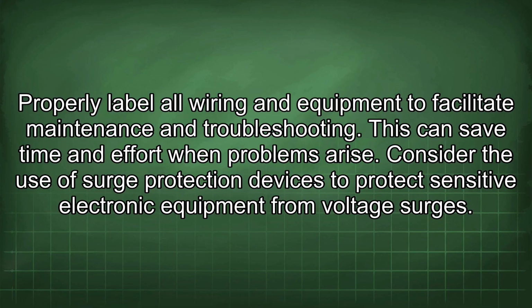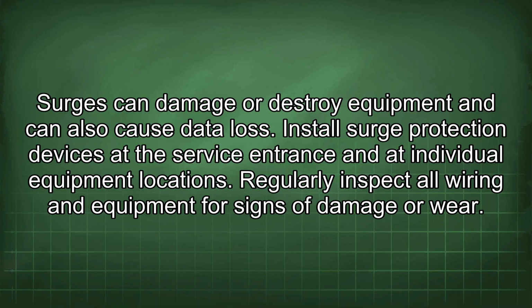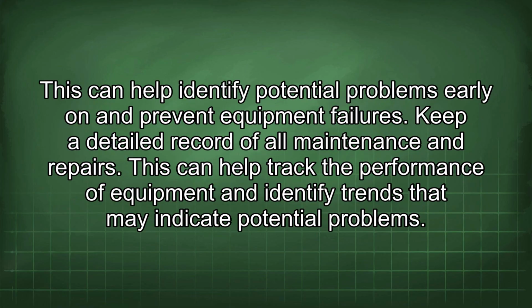Consider the use of surge protection devices to protect sensitive electronic equipment from voltage surges. Surges can damage or destroy equipment and can also cause data loss. Install surge protection devices at the service entrance and at individual equipment locations. Regularly inspect all wiring and equipment for signs of damage or wear. This can help identify potential problems early on and prevent equipment failures. Keep a detailed record of all maintenance and repairs. This can help track the performance of equipment and identify trends that may indicate potential problems.